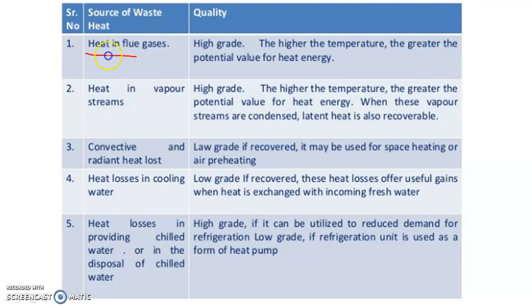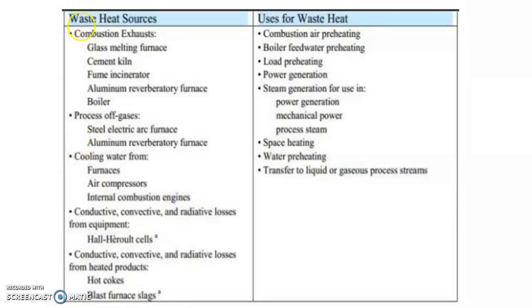These are the sources of waste heat: heat in the flue gases, heat in the vapor streams, convective and radiant heat losses, heat loss in cooling water, and heat losses in providing chilled water or in the disposal of chilled water. The waste heat sources are glass melting furnace, cement kiln, fume incinerator, aluminum reverberatory furnace, boiler, process gases, steel electric arc furnace, cooling water from furnace, air compressor, internal combustion engines, conductive, convective and radiative losses from equipment, hot coke and blast furnace. They are used for combustion air preheating, boiler feed water preheating, load preheating, and power generation. So these are some of the uses for waste heat.